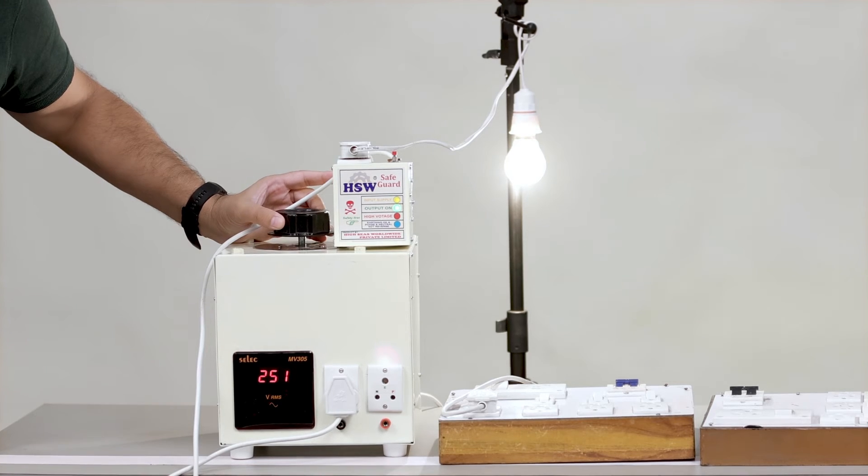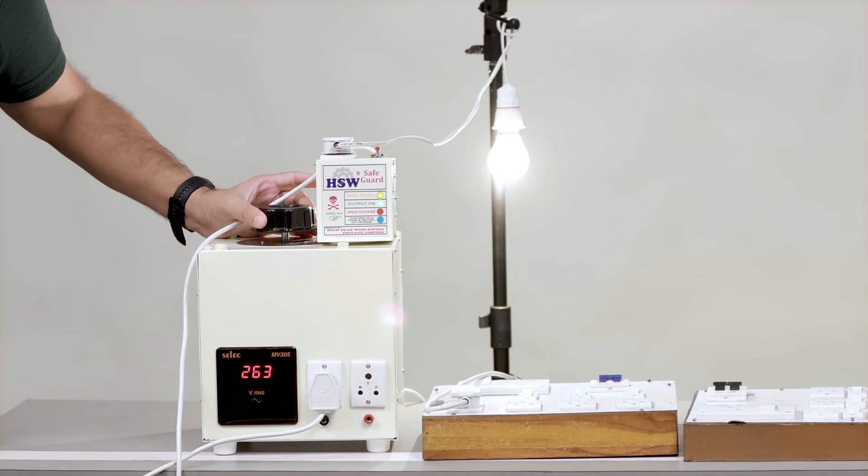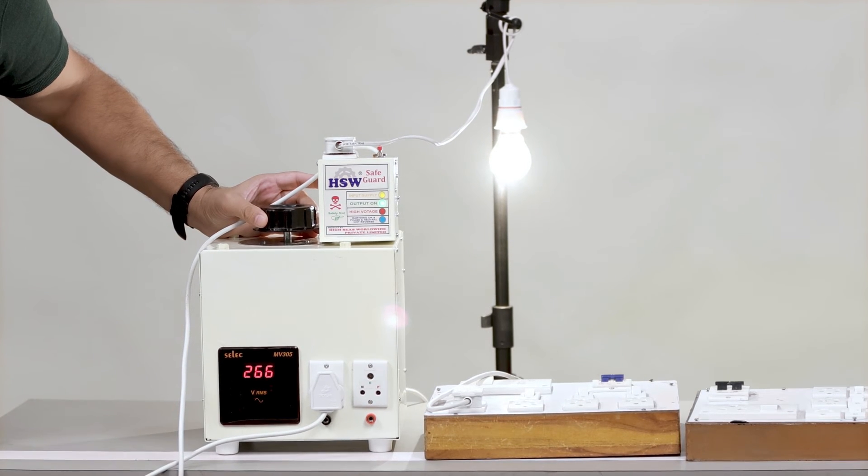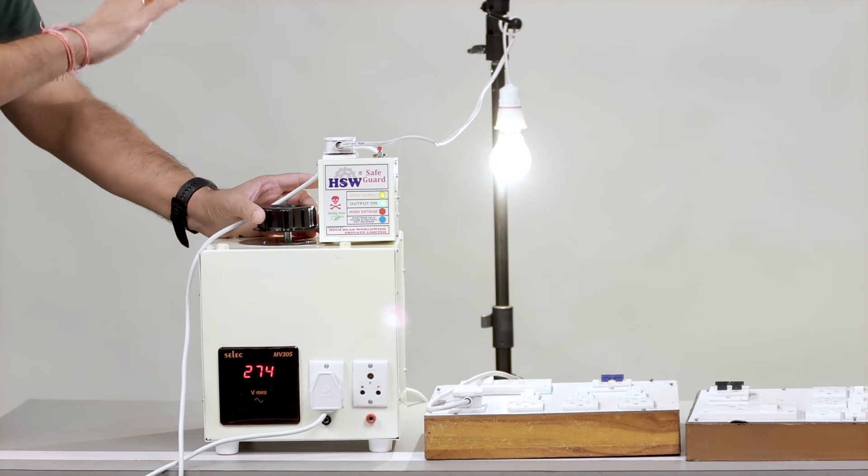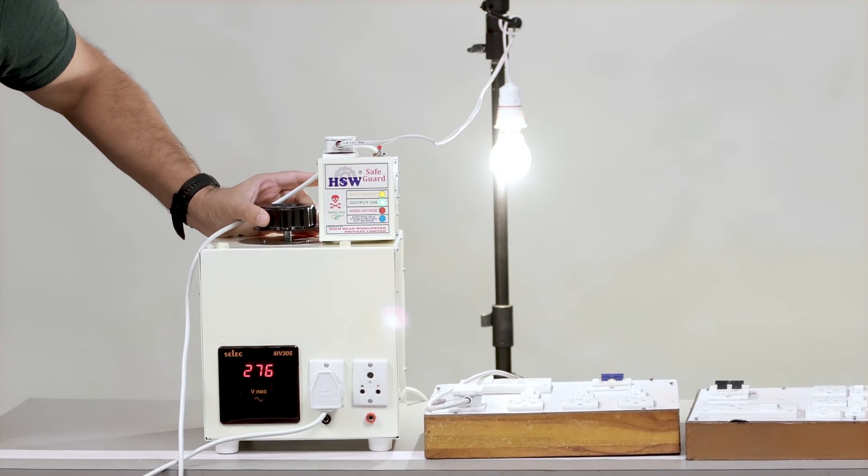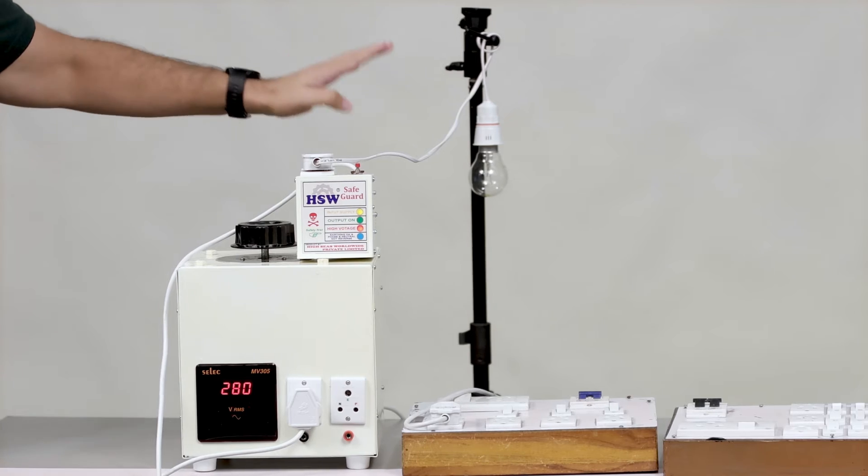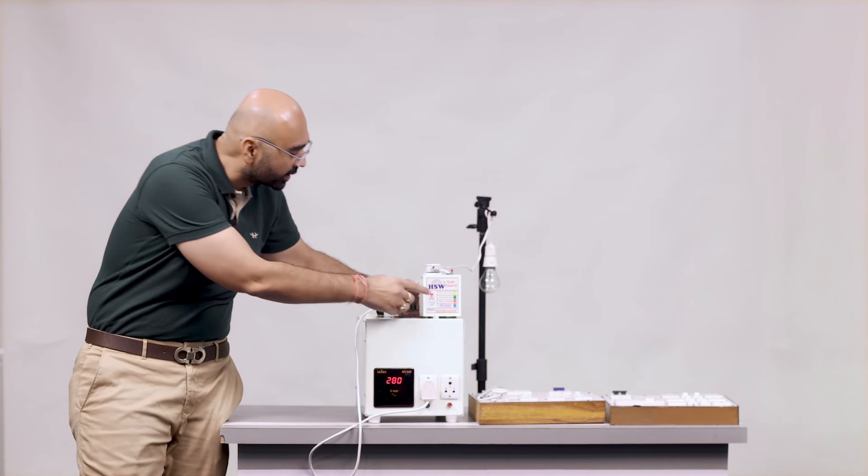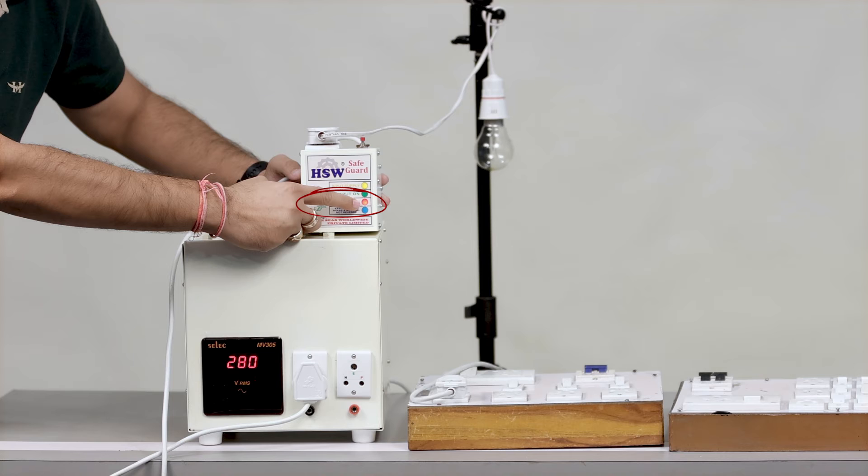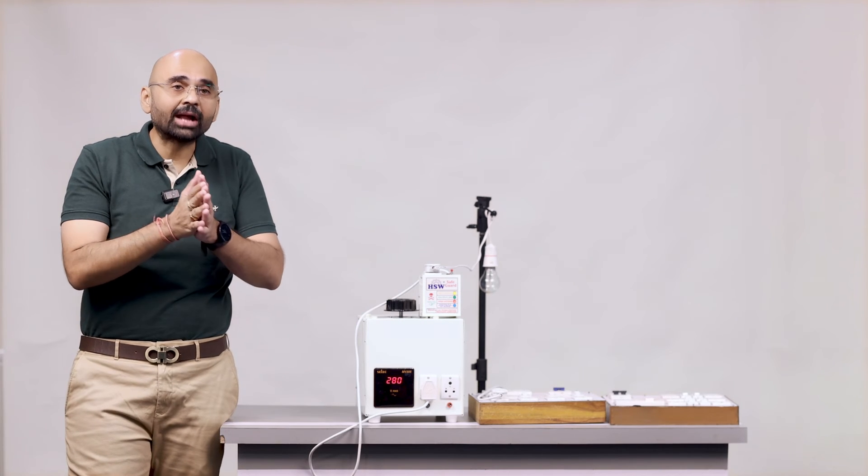So see right now we are taking straight away to 263. Now we will gradually increase it. See up to 274 our bulb is on. Now 275, as soon as it crossed 276 the light is off and over here you can see high voltage is on and this sign will be on till the time the voltage will go down.